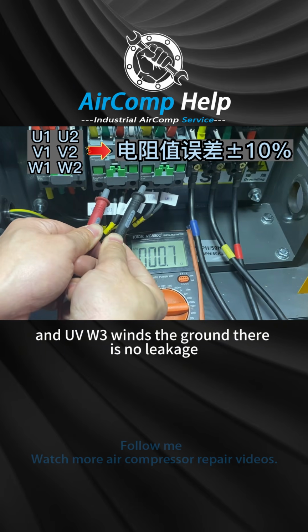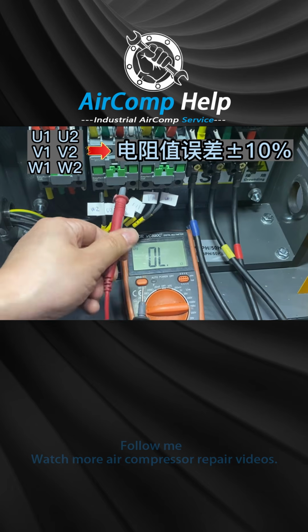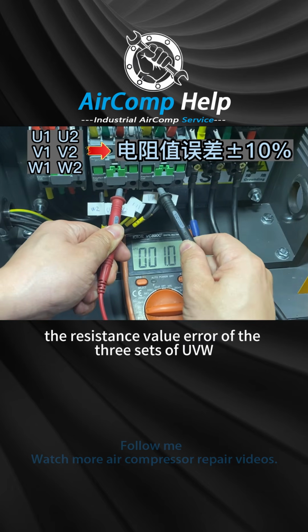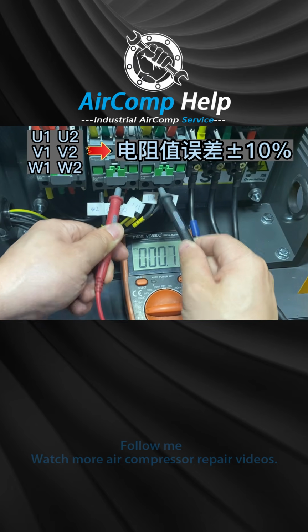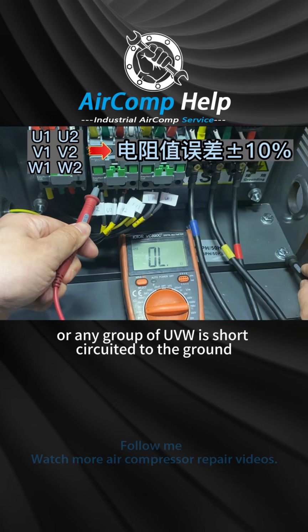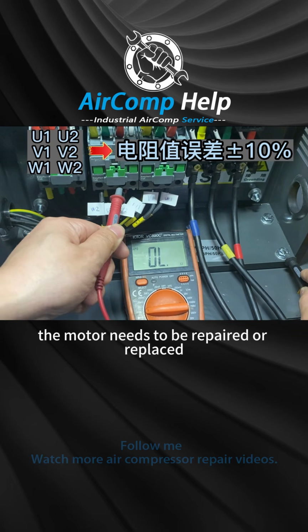And check the UVW 3 windings to ground, there should be no leakage. If the resistance value error of the 3 sets of UVW windings is 10% or more, or any group of UVW is short-circuited to the ground, that's the problem with the motor. The motor needs to be repaired or replaced.